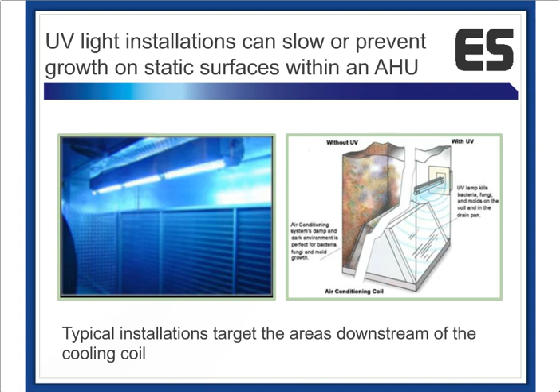There are other types of systems. Just one example here: all of the air that we're talking about passes through ductwork systems, and all of those are susceptible at some point to organism growth. This is just one example of a maintenance method using ultraviolet light to help manage the organisms that could be growing in there. Probably one of the other primary things we look at in ventilation systems specifically is air filtration. All of our air filters for patient care areas in clinical spaces, according to the requirements standards today, are a minimum of 90%. That's if they're installed correctly.